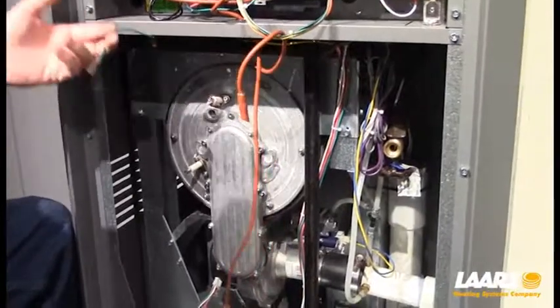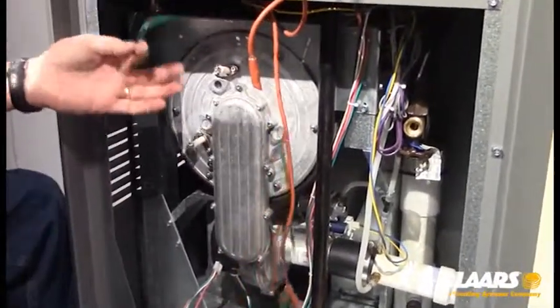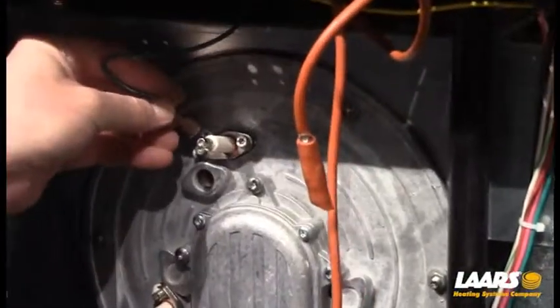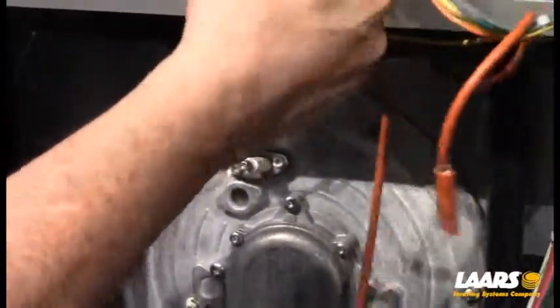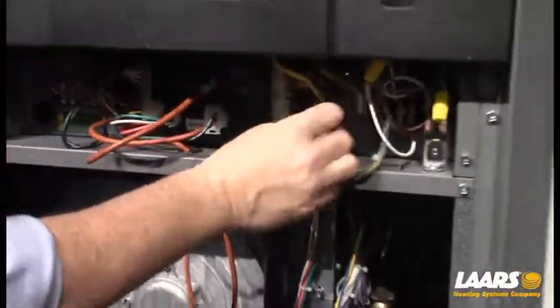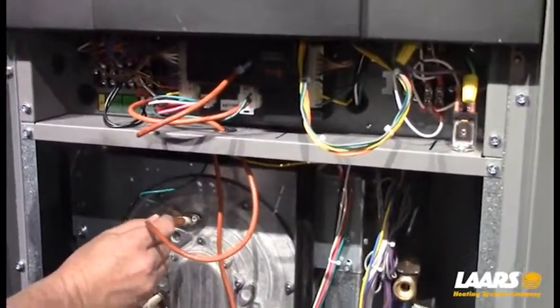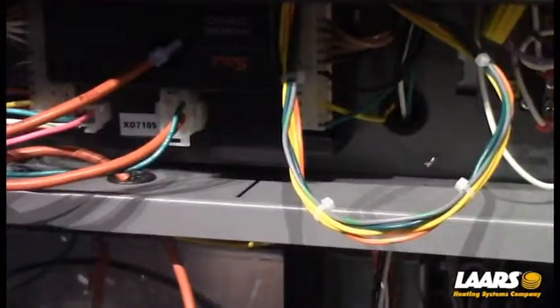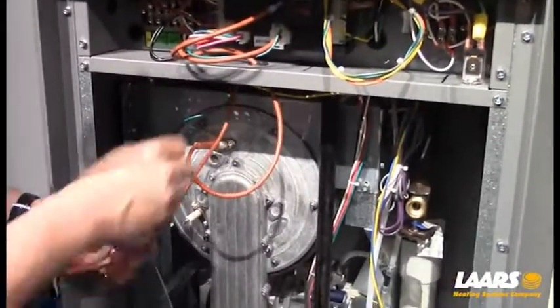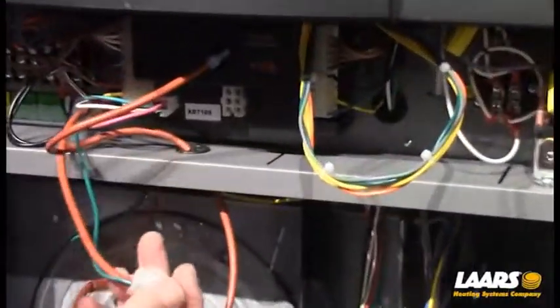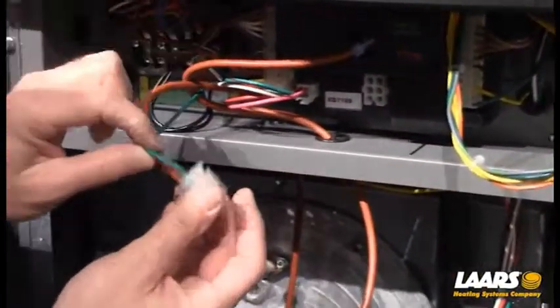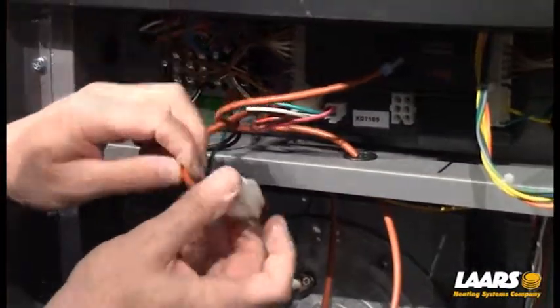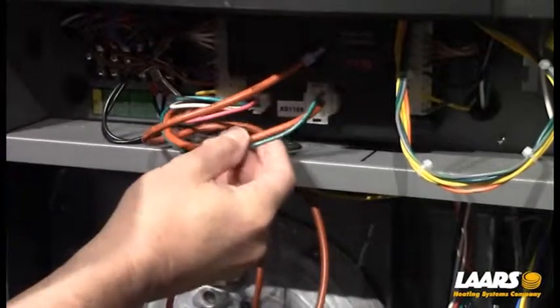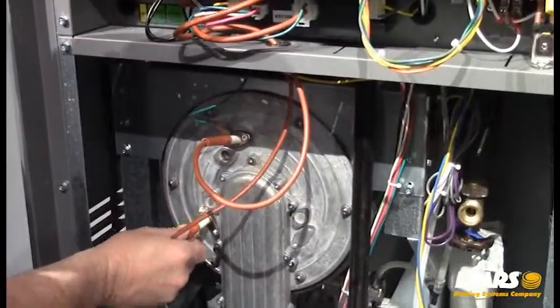So next, we want to wire back up our igniter and our flame rod. So the igniter, there's a ground lug. So just land your ground lug. And we want to make sure we've got the ignition cable. So the ignition cable comes out of the center of the Honeywell control. All right, that's our ignition cable. We're going to land that on the igniter. And the flame rod lead comes up to this Molex plug right here. And this is your flame rod, and that's your ground. The ground again goes to the igniter, and flame rod goes here to this Molex plug. So we're going to trace that down. There's our flame rod wire.